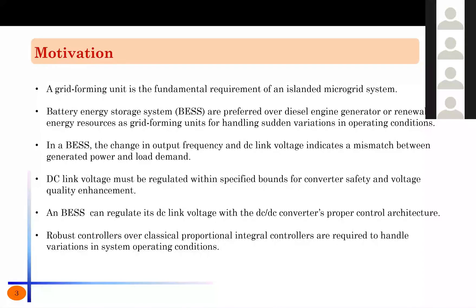Starting with the motivation: the grid-forming unit is the fundamental requirement of an islanded microgrid system because they don't have any voltage and frequency support for themselves. Therefore, a grid-forming unit is very important for an islanded microgrid system. However, battery energy storage systems are preferred for handling sudden variations in operating conditions over diesel engine generators, which have slow response time, or renewable energy resources due to their intermittent nature. In a battery energy storage system, the change in output frequency and DC link voltage indicates a mismatch between the generated power and the load demand.